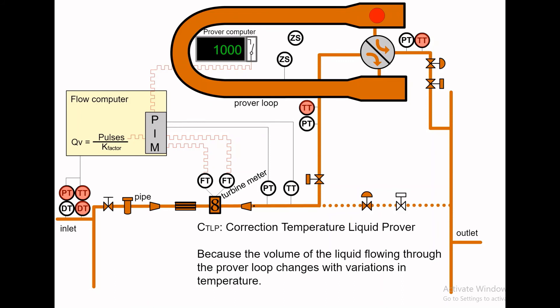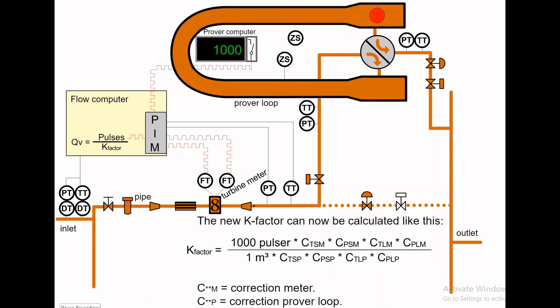CTLP, Correction Temperature Liquid Prover, makes the correction required because the volume of the liquid flowing through the prover loop changes with variations in temperature. CPLP, Correction Pressure Liquid Prover, makes the correction required because the volume of the liquid flowing through the prover loop changes with variations in pressure. This is the formula to calculate the new k-factor.